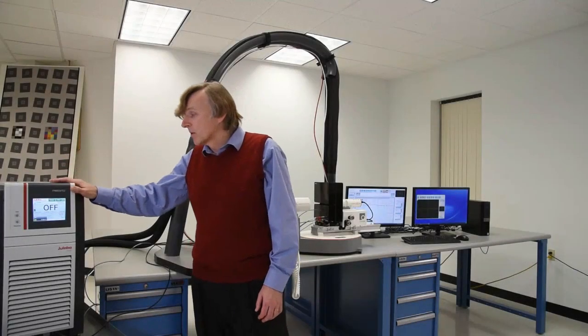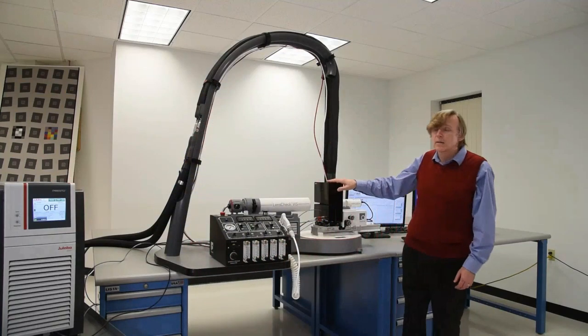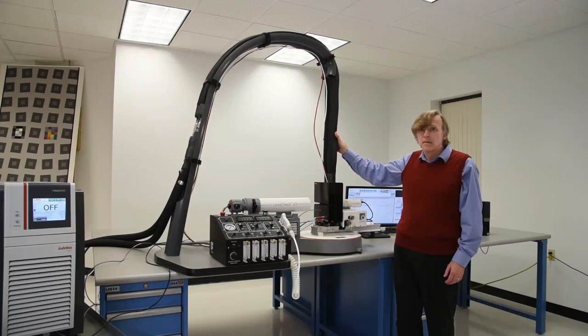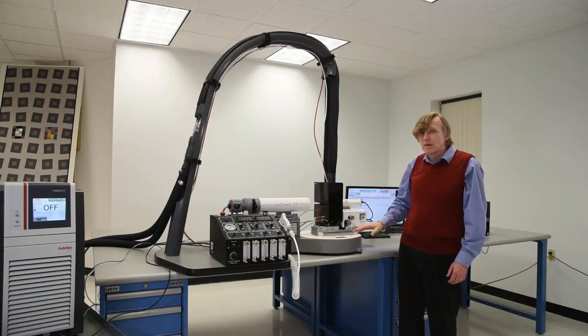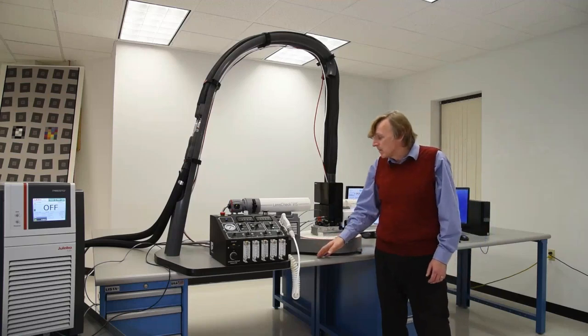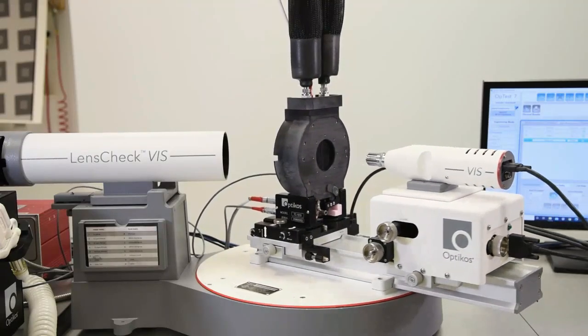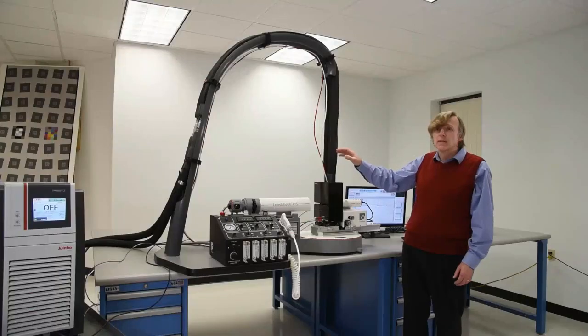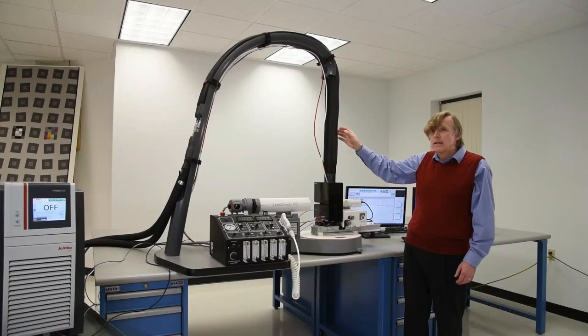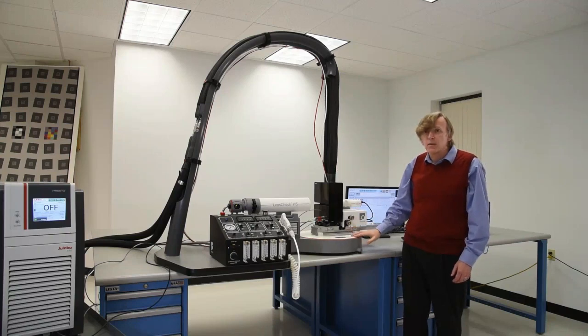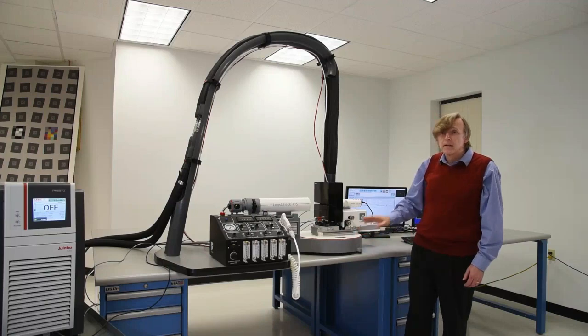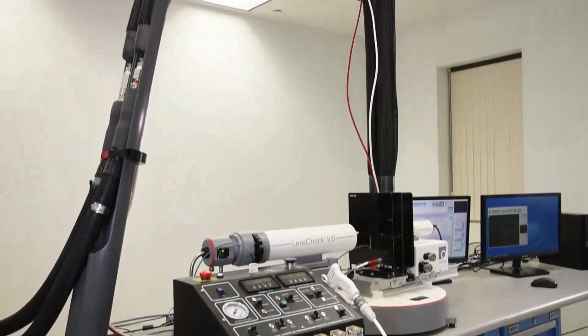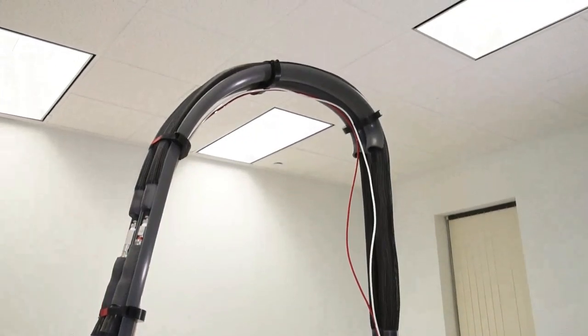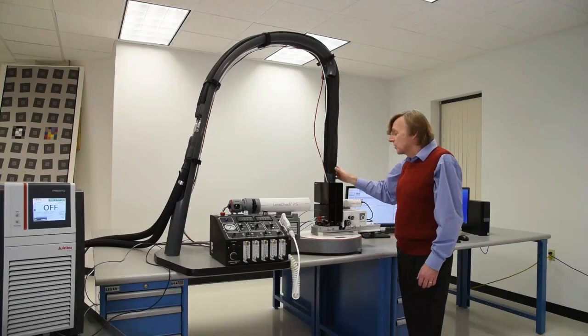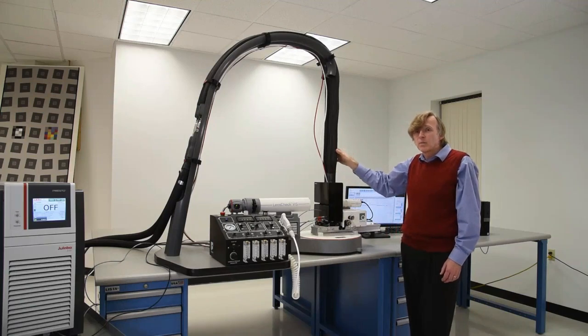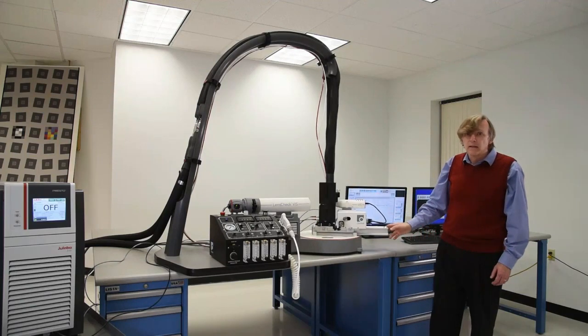The fluid circulates from the thermal controller to the thermal chamber in a closed-loop manner through two insulated hoses that you see here. If the lens were to remain fixed on the test bench, we could simply drape these hoses along the table. But because we might want to make off-axis measurements on the lens, we must permit it to rotate. It is for this reason that the hoses enter the chamber from above, so they can be placed as close as possible to the axis of rotation of the platform on which the lens is mounted. This is the function of the self-supporting troughs that you see here, which we affectionately refer to as the skyhook. They guide the hoses down into the thermal chamber from above, from a height that is sufficient to support the wind-up that occurs when the lens rotates off-axis.